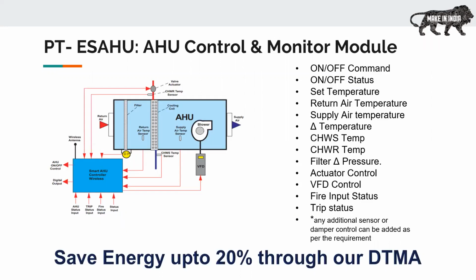Now, there are cases in a building where the existing BMS is limited to only on-off, but there is no way to control their chilled water consumption. For those scenarios, we have a miniature version of this module where we can know the on-off status of the AHU, measure the return air temperature, measure the supply air, the delta T of it, then measure the chilled water supply and chilled water return. With these 4 parameters, we regulate the actuator control between 0 to 10 volt DC and take the actuator feedback.